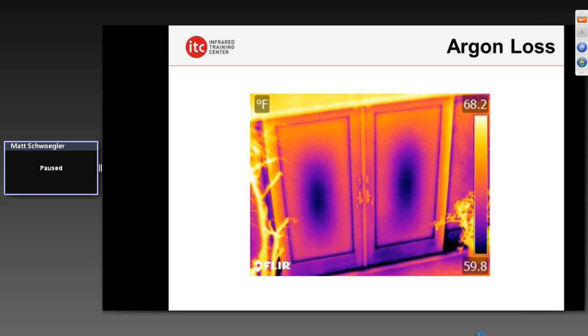We can evaluate window performance. In this case, two windows that have lost their argon — the argon has depleted over time, creating a vacuum inside between the insulated glass units. As that argon seeps out, air molecules are not large enough to get back in, creating a negative pressure which draws those panes together. Now the window has lost much of its performance in the center because of that loss of argon. We've got more conductive heat flow occurring at these points than at other portions of the window, showing a potential issue with these windows not performing as well as they used to.